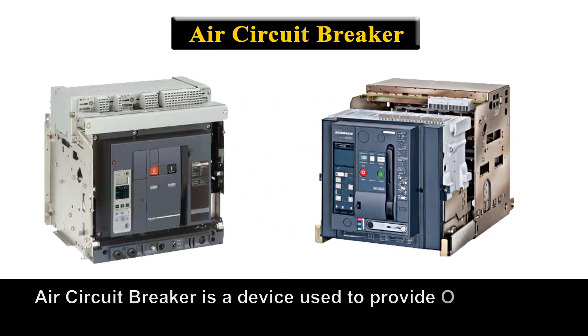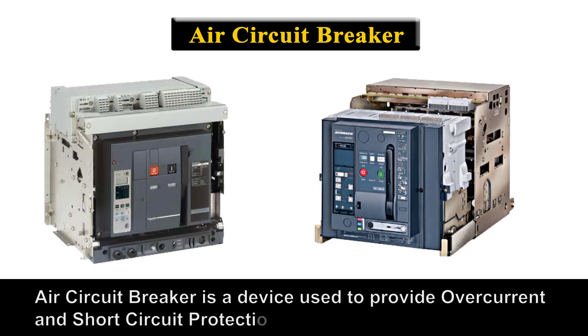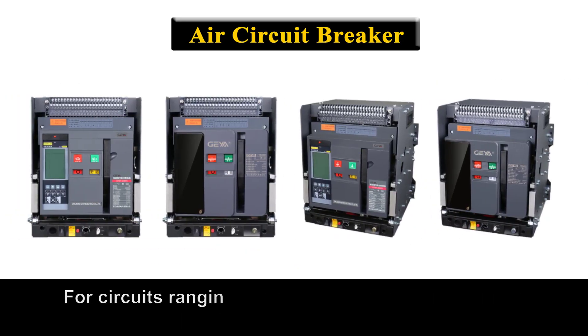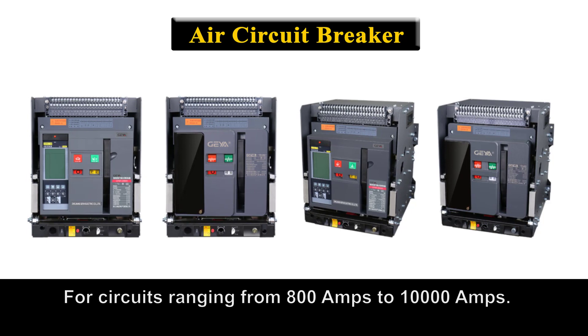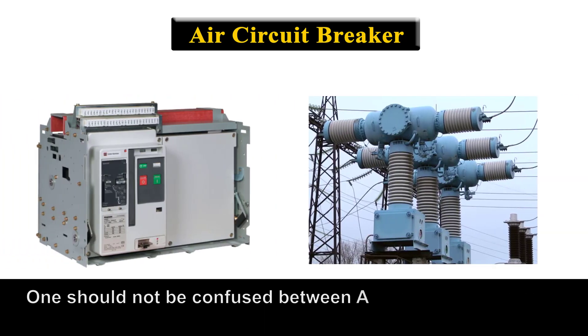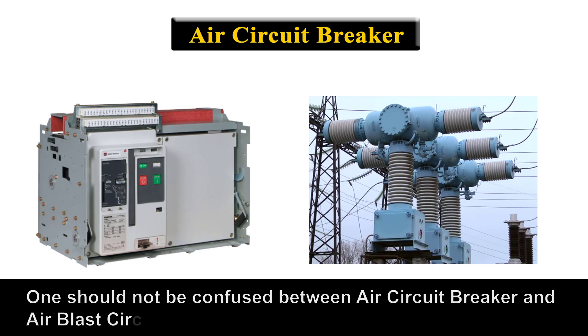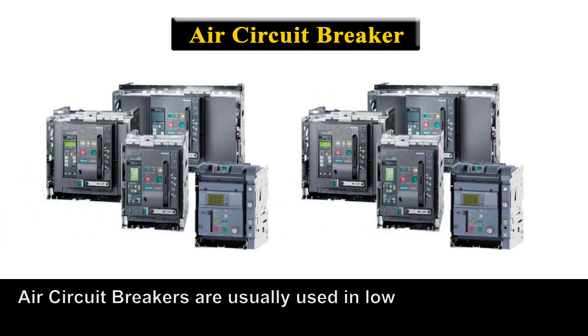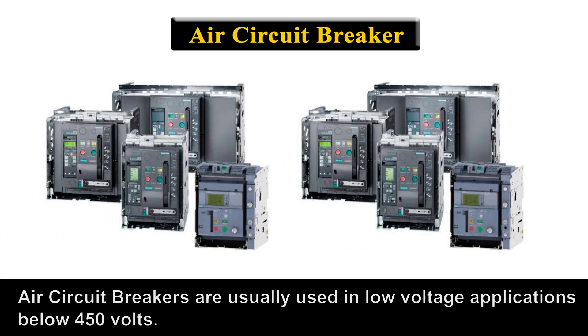An Air Circuit Breaker is a device used to provide overcurrent and short circuit protection for circuits ranging from 800 A to 10,000 A. One should not be confused between Air Circuit Breaker and Air Blast Circuit Breaker. Air Circuit Breakers are usually used in low-voltage applications below 450 volts.